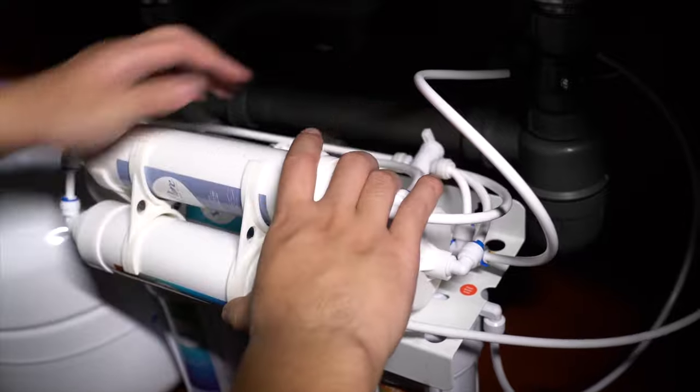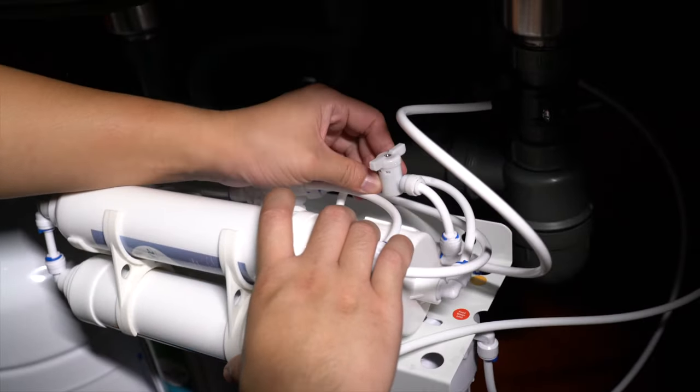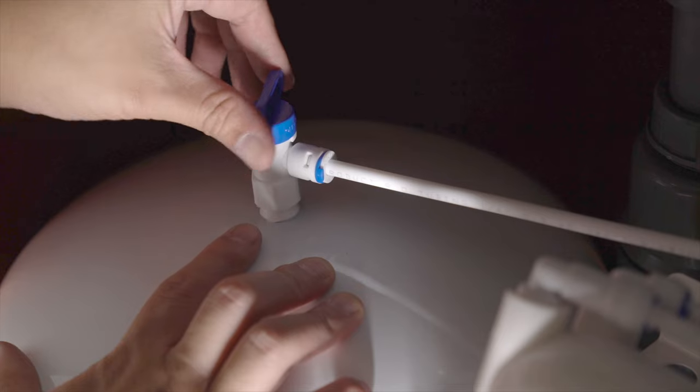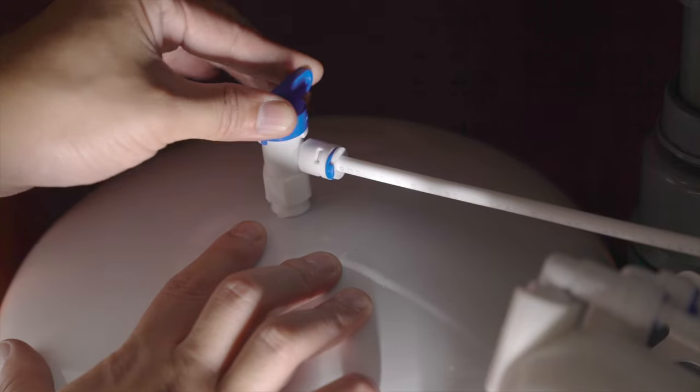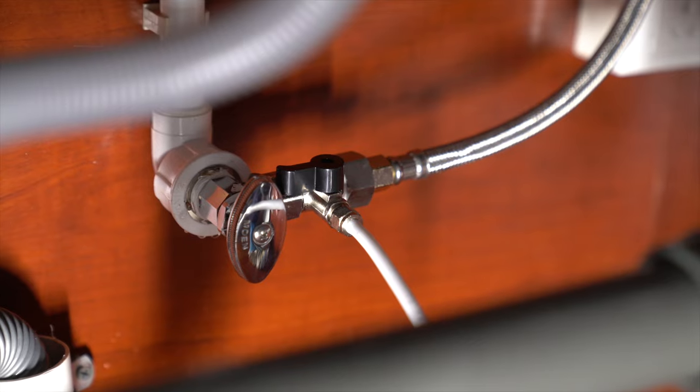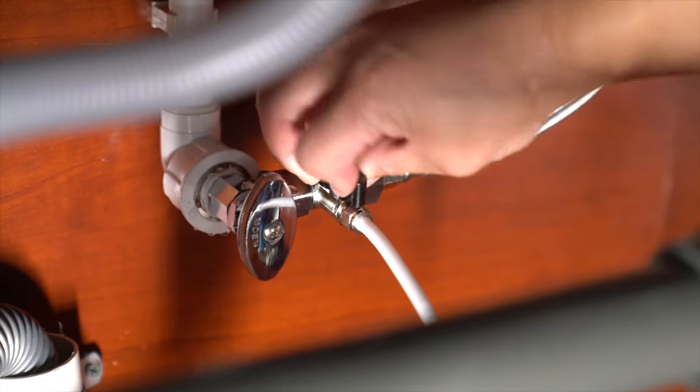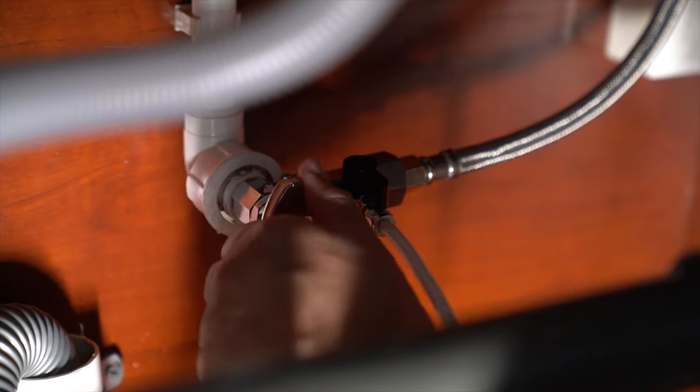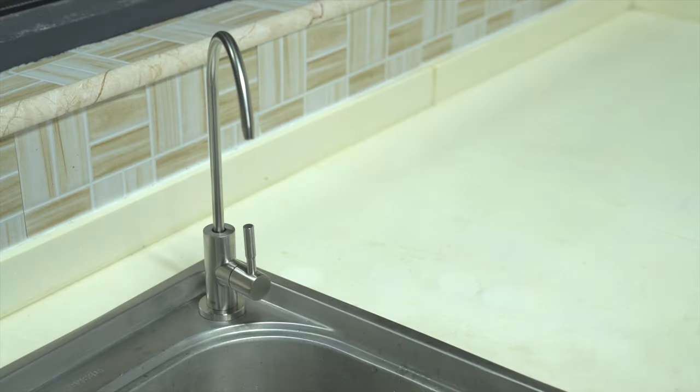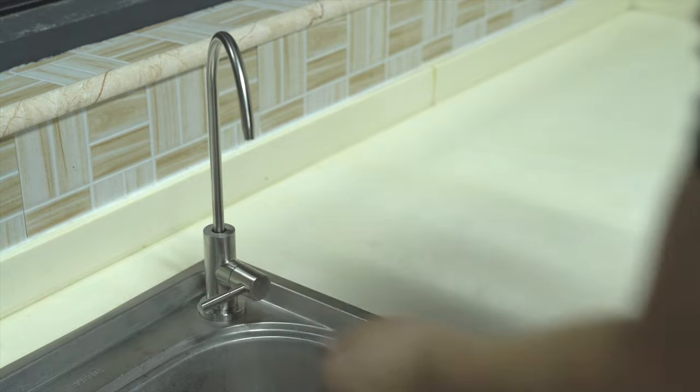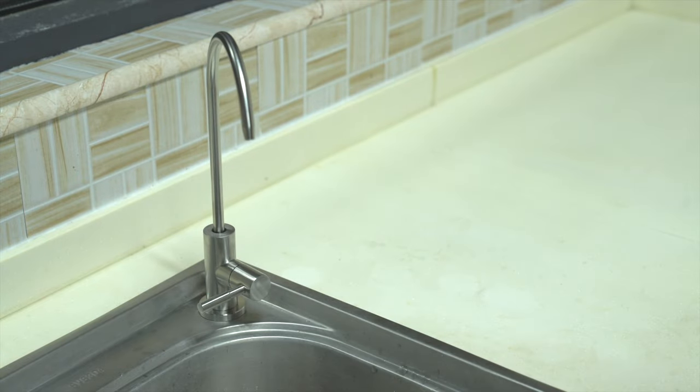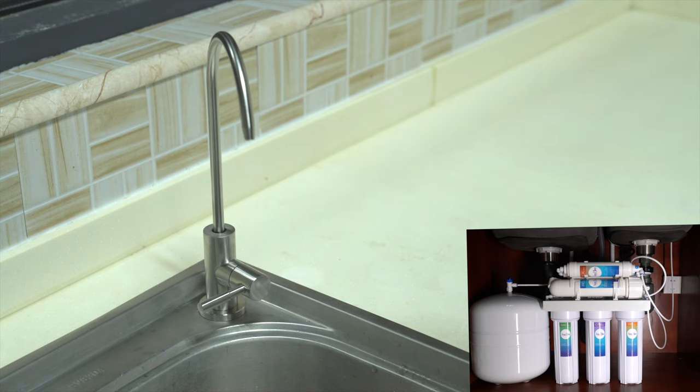The next stage is to commission and flush the system ready for use. One, ensure the manual flush valve on the T1 central unit is closed. Two, close the pressure tank ball valve. Three, turn on the cold water shutoff valve and the feed water adapter. Four, open the faucet and allow the water to run to drain to rinse all components. During this time, review all connections and make sure there are no water leaks.